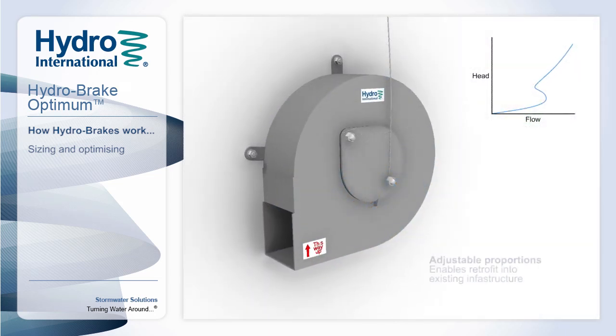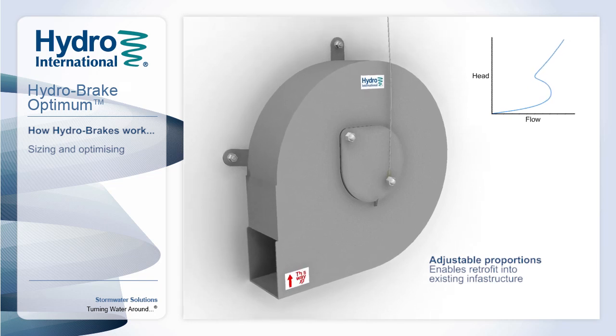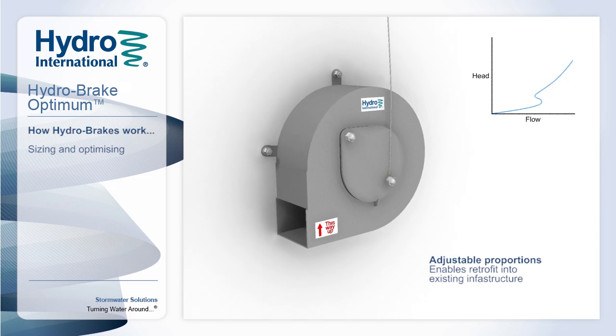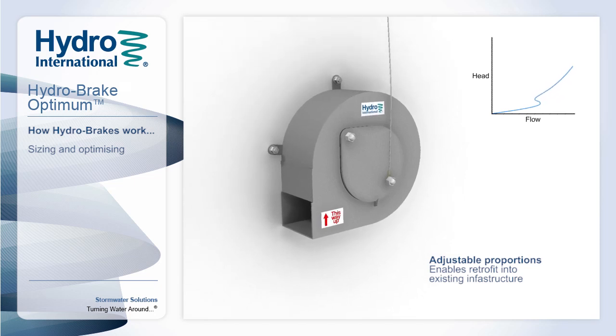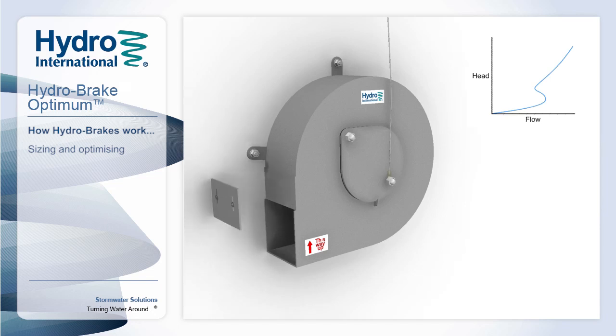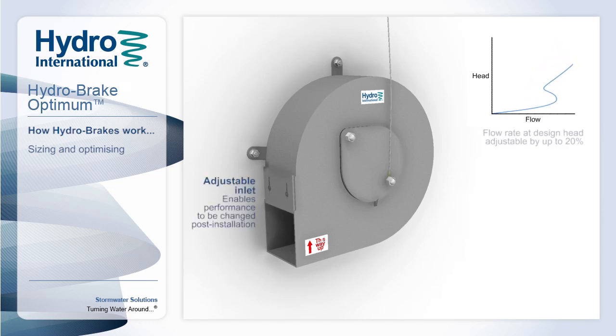The physical dimensions of the Hydro-Brake Optimum can be adjusted, which is of particular benefit for retrofit schemes, as it allows units to be designed to fit to existing infrastructure, eliminating costly replacement or regeneration works. The Hydro-Brake Optimum is future-proofed against climate change and future development through the optional adjustable inlet, allowing flows to be adjusted by up to 20% post-installation.